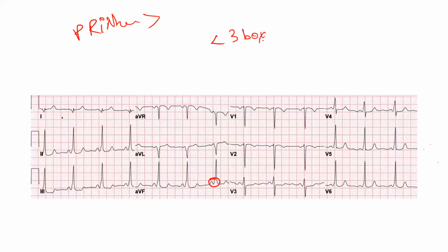If you see here, this is the standardization. See, this has crossed a 10 millimeter height. Yes or no? 10 millimeter is equivalent to 1 millivolt amplitude. You get a 10 millimeter deflection only when the ECG is reading at 25 millimeters per second.